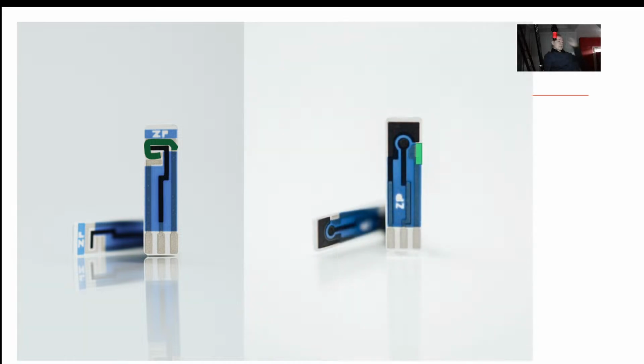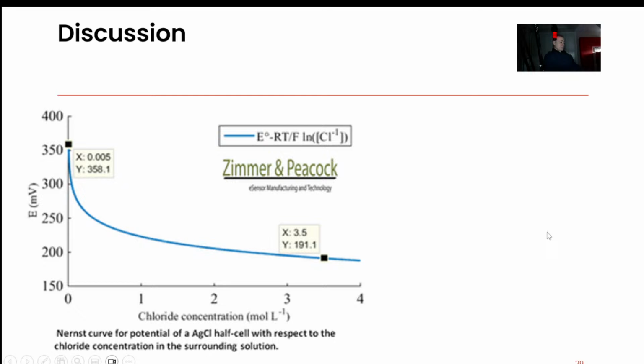Back to the reference electrode. Sometimes if we need to protect the reference electrode, we put an extra layer on top of it, and this is to fix the chloride concentration in place. Now the reality is that you can't fix the chloride in place. It does actually eventually diffuse away. So I just put a discussion here: if you're in the blood, then I wouldn't overthink this, by the way, because I think there the chloride is quite fixed. But for example, in the past, we would have thought it was a good idea to load up the reference electrode with loads of chloride so that we had this kind of reservoir of chloride.